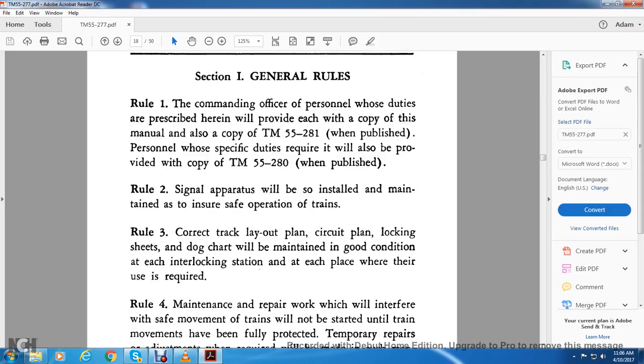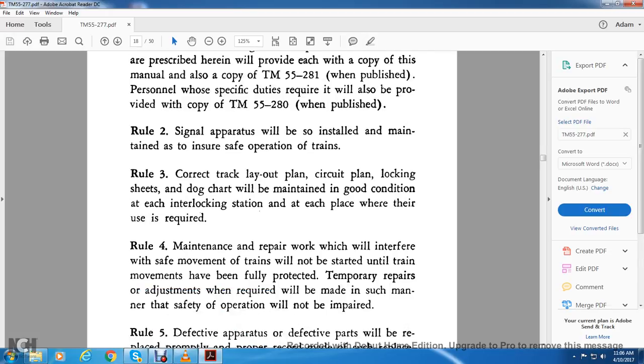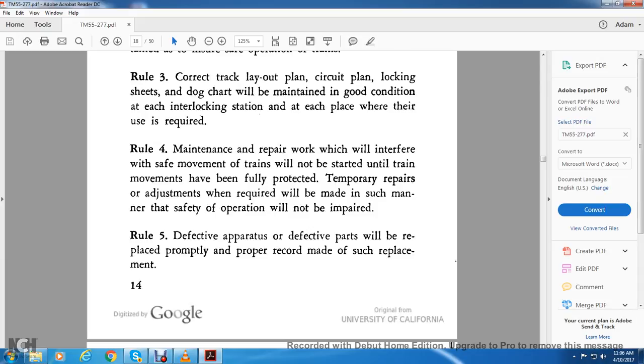Rule 2. Signal apparatus will be installed and maintained to ensure safe operation of trains. Rule 3. Correct track layout plans, circuit plans, locking sheets, and dog charts will be maintained in good condition at each of the interlocking stations and each place where their use is required. Rule 4. Maintenance. Repair work which will interfere with the safe movement of trains will not be started until train movement has been fully protected. Temporary repairs or adjustments, when required, will be made in such a manner that the safety of operation will not be impaired. Rule 5. Defective apparatus and defective parts will be replaced properly, and a proper record made of such replacements.